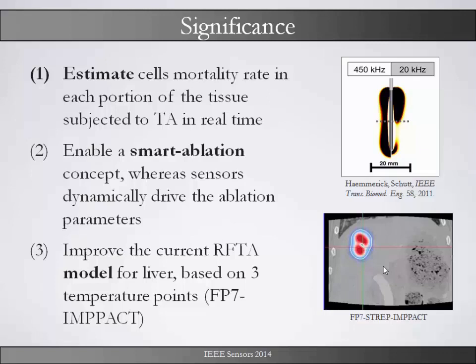As you can see, most of the temperature is distributed alongside the needle, and only a small distribution is perpendicular to it. The important point is that if you treat cancer with thermal energy, you don't want to kill healthy cells. If you apply too much temperature there is a high probability of killing healthy cells, but if you apply not enough temperature it could be that cancer cells survive and spread over the body. So it is very important to measure the radio frequency ablation online and use these parameters to adjust the treatment.